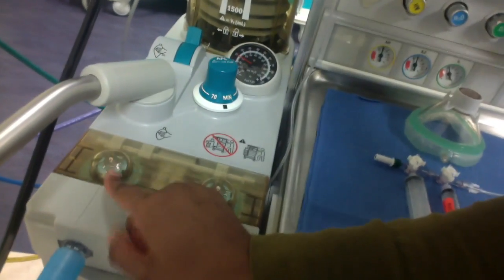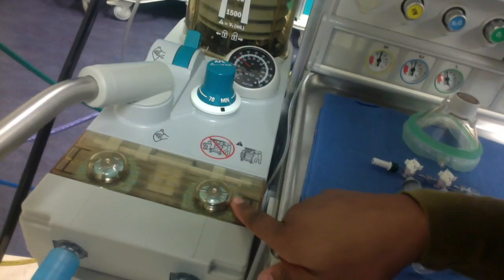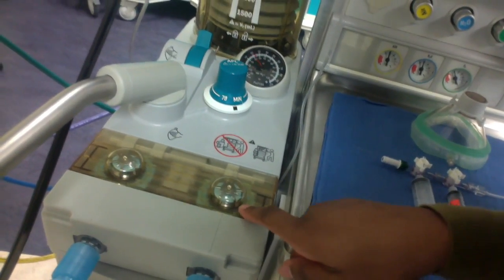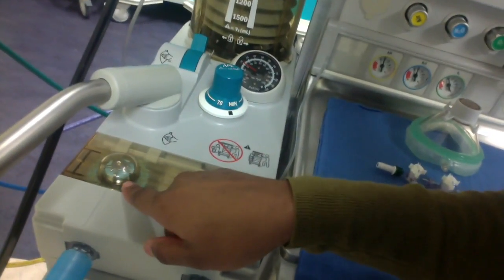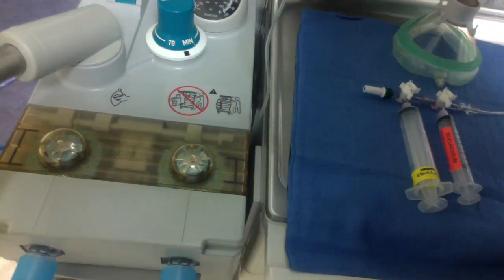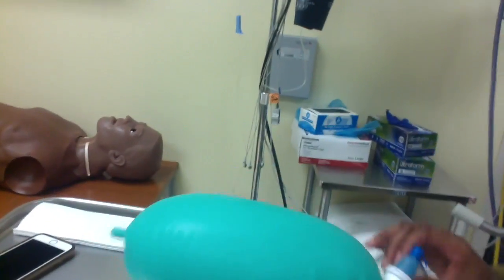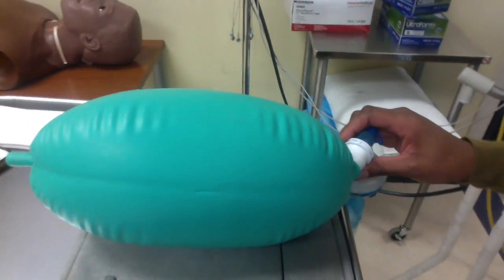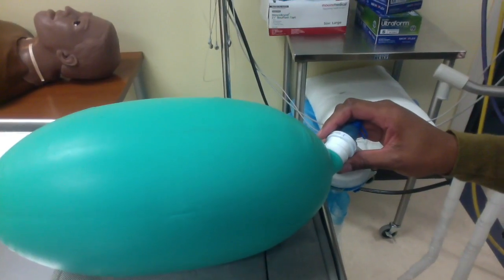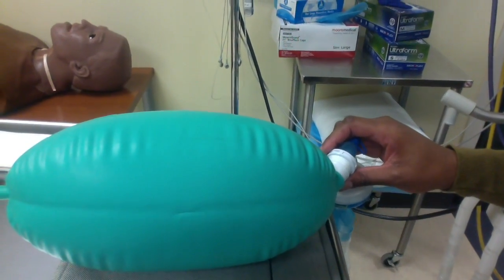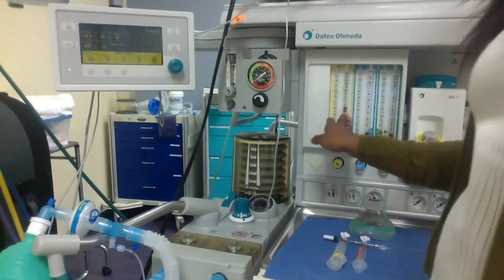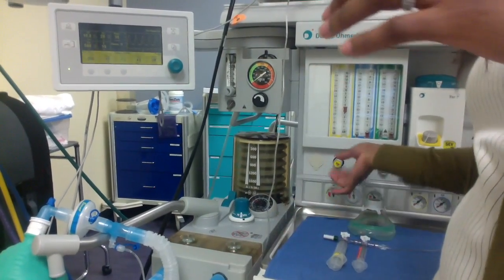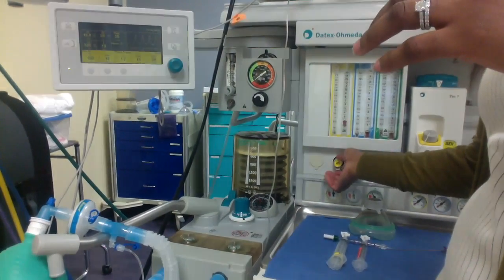On inspiration, the inspiratory valve will float, and this will stay seated. On expiration, the expiratory valve will float, and the inspiratory will stay seated. And so you can just see and look at those. You will also be able to see here, with my artificial lung, it inflating and deflating. So it's on 5 liters. I've checked all the things that I need to check. So I'll do that again at a lower flow, let's say 2 liters per minute.